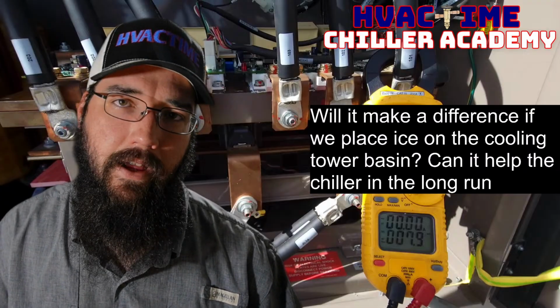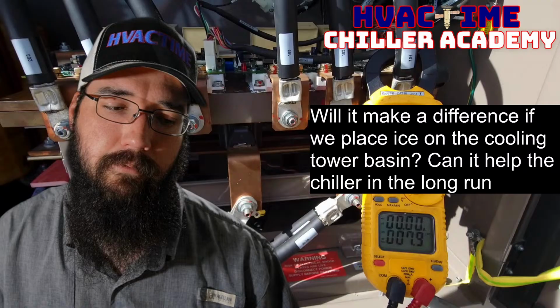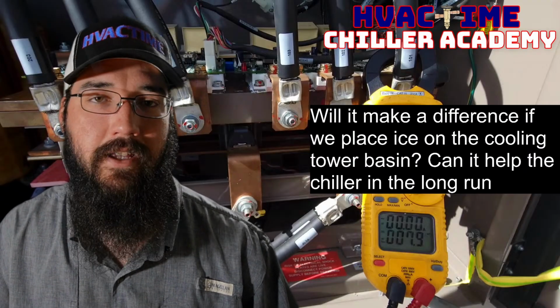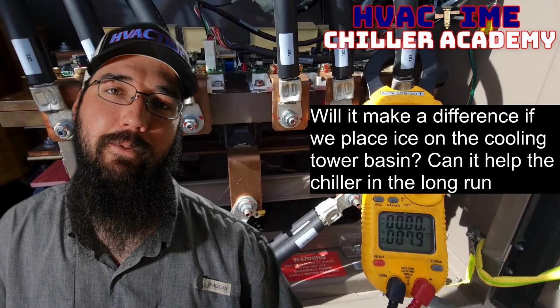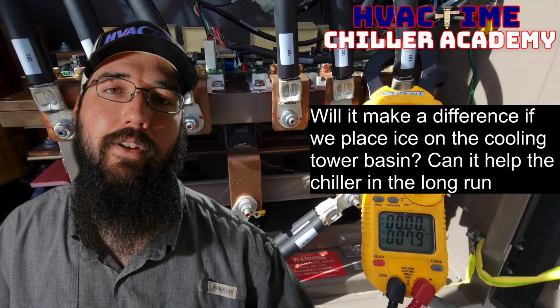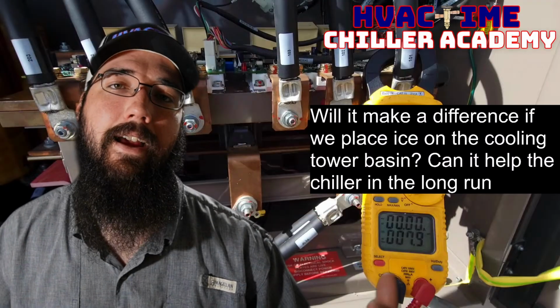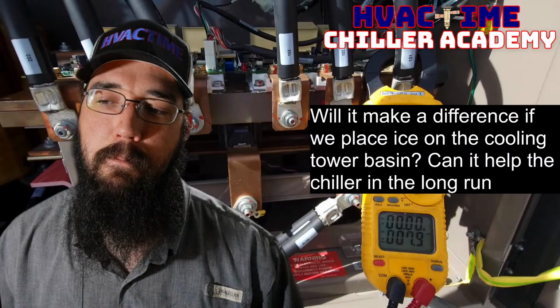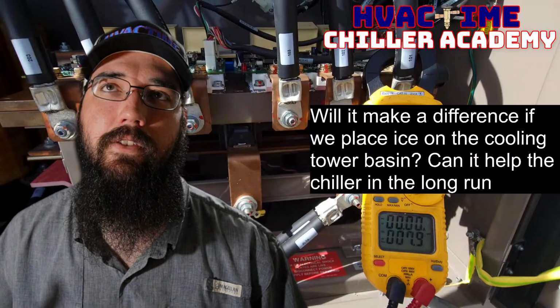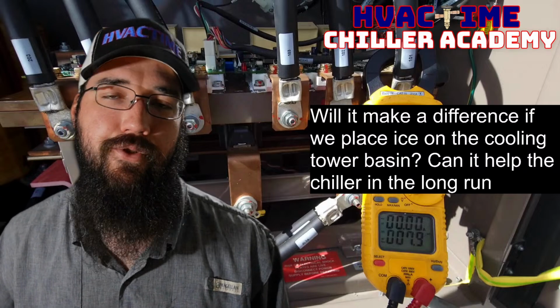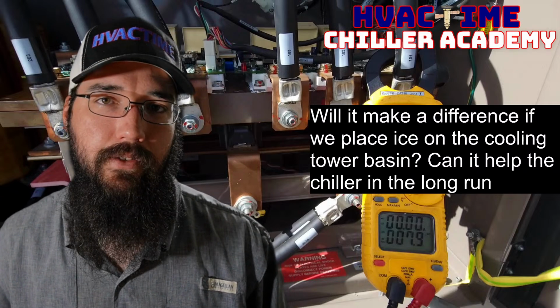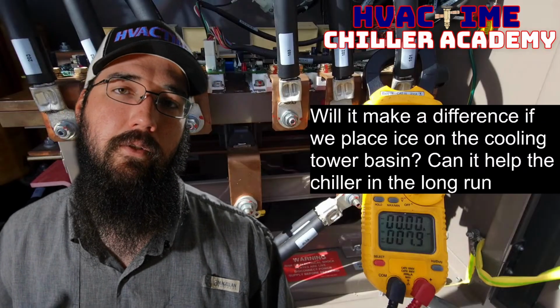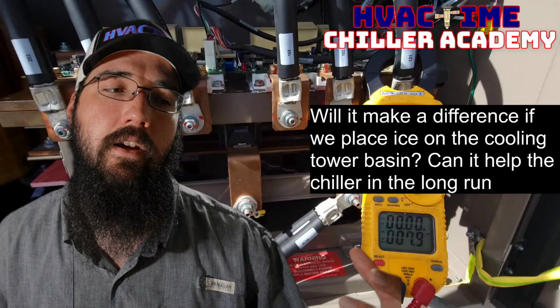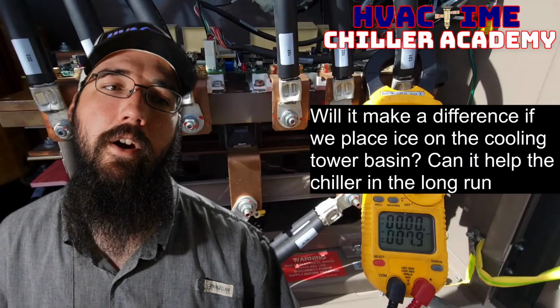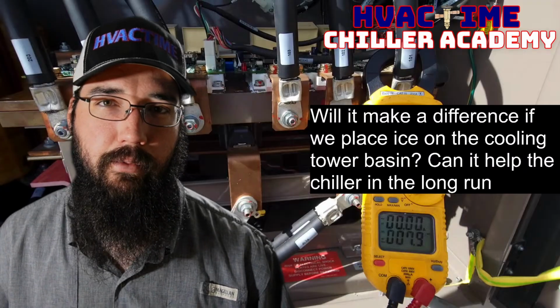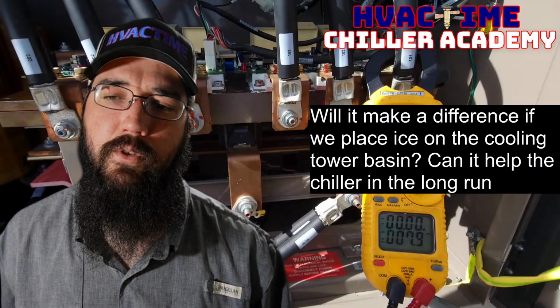And if we add enough ice and it doesn't get sucked into the pumps or anything, because you don't want that, but if we add enough ice and we can run the system safely, then yeah, we could get that tower water theoretically down as far as we wanted to go. But at that point, you're adding another form of refrigeration to the cooling tower process. And we're no longer basing our ability to make set point off of what the ambient conditions are anymore and our ability to evaporate inside of those parameters. Does that make sense?